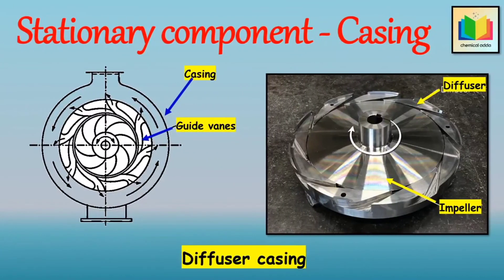The third type of casing is used in diffuser type or turbine pumps. In this type, guide vanes or diffusers are interposed between the casing chamber and the impeller. The impeller is surrounded by a series of guide vanes mounted on a ring called a diffuser ring. The conversion of kinetic energy into pressure energy is more efficient with this type compared to the volute type. There is a gradual change in the direction of fluid, so losses are kept to a minimum, and improved efficiency is obtained over a wider range of capacities. This construction is often used in multi-stage high-head pumps.